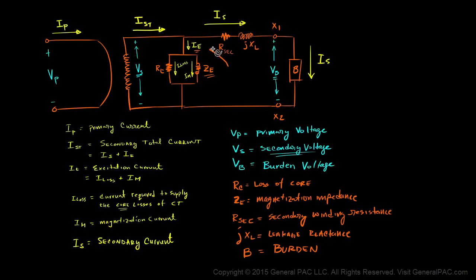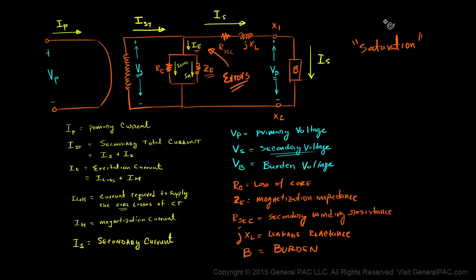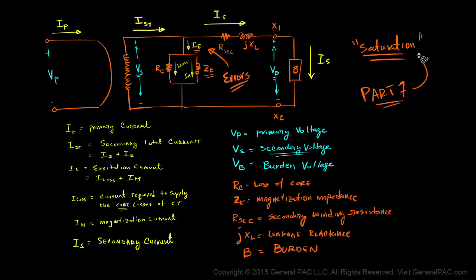The excitation current implies the errors of a current transformer, and those errors are often called saturation. We hear that term a lot — the current transformer is going to saturate. The saturation or errors of a current transformer are modeled by this excitation current flowing through the magnetization branch, which is a non-linear value. In Part 7, we're going to talk about saturation from a CT model's perspective and correlate saturation with the excitation current, the secondary voltage, and the role that burden plays in all of that.